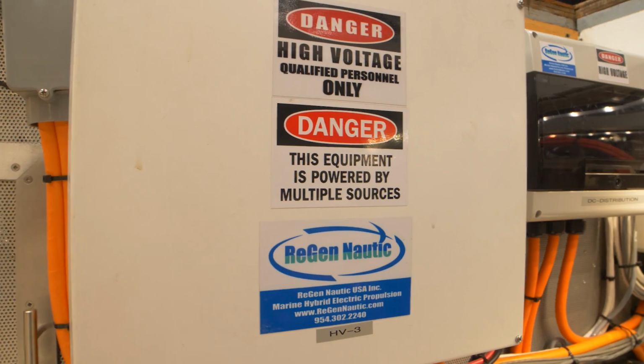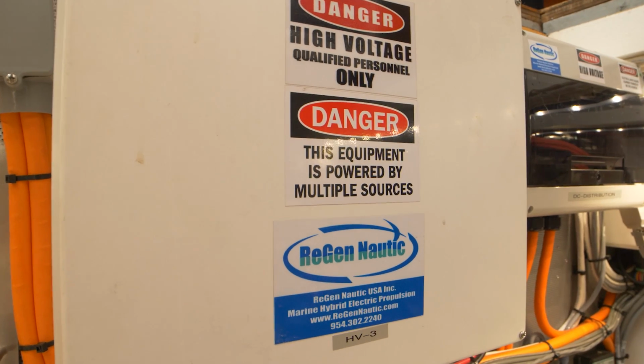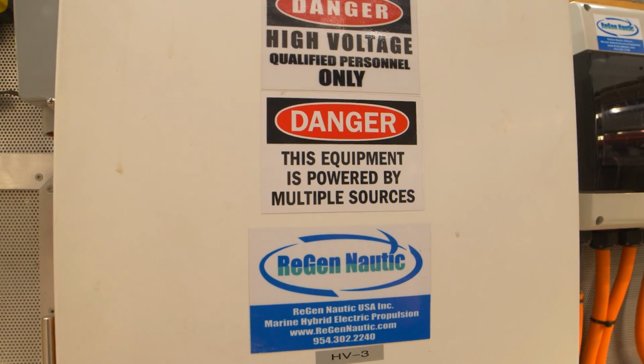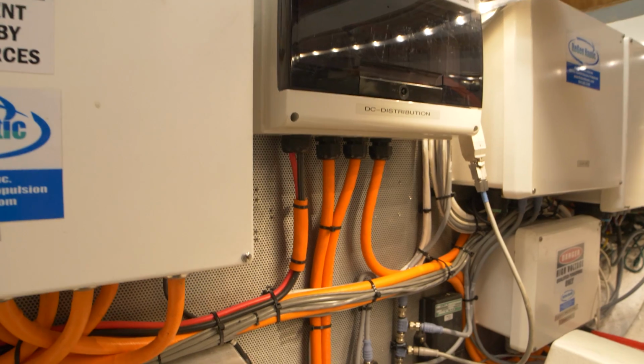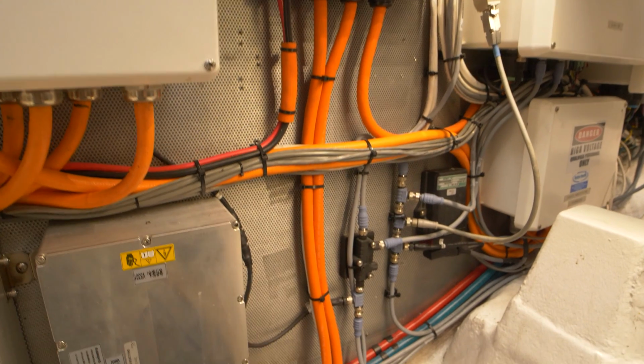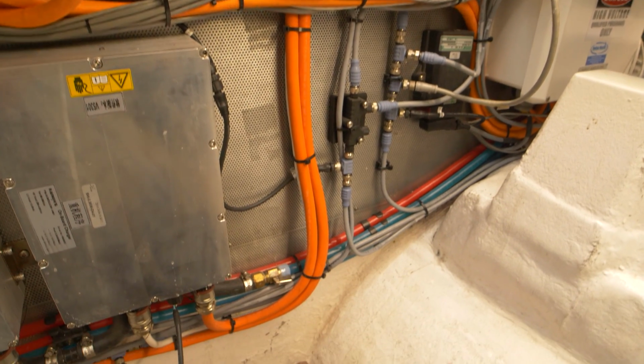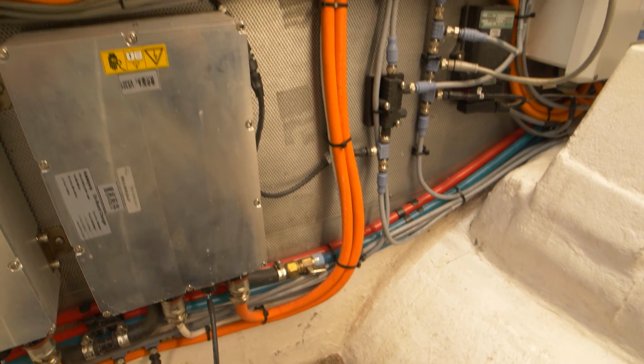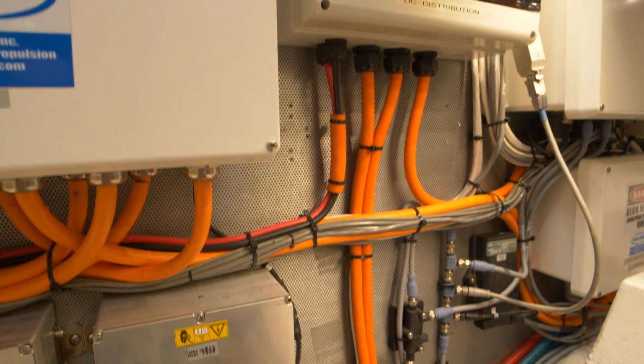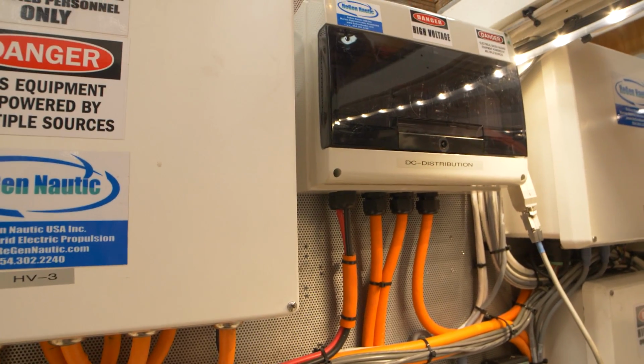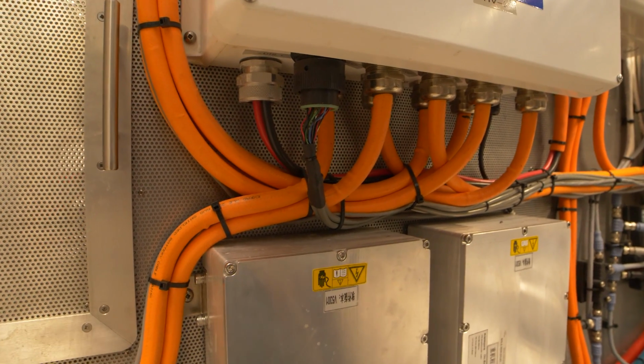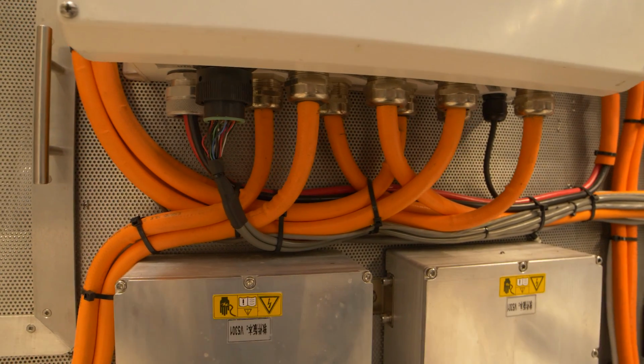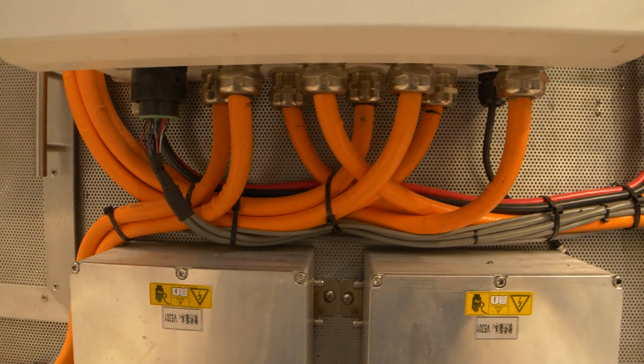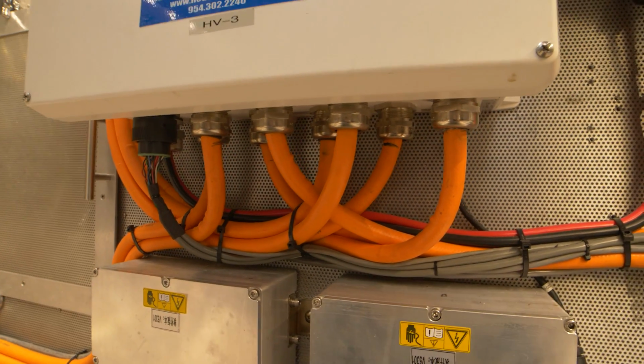It must be noted that if you notice the orange cables, that is pilot line. It's an automotive industry standard. You cannot be shocked by this system. If there's any grounding or short circuiting, limit switches automatically open the contactors and drop the whole system voltage to 50 volts. Inside each high voltage box there are limit switches, so if you were to pull the cover off of either of the high voltage boxes, the system immediately drops to 0 voltage.